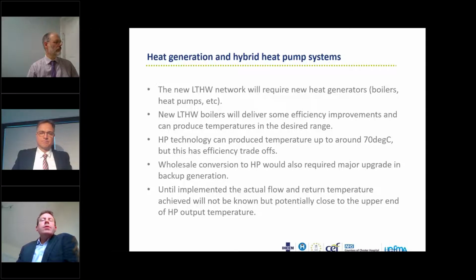So with this project we're going to move to low temperature hot water. Wouldn't it be nice if we could put some sort of heat pump technology in today? We'll need low temperature hot water boilers for this new network, which will deliver some efficiency improvement. But we can also look at putting in heat pump technology, because there are heat pumps out there now that will produce up to around 70 degrees with an efficiency trade-off, but it still has an overall benefit.